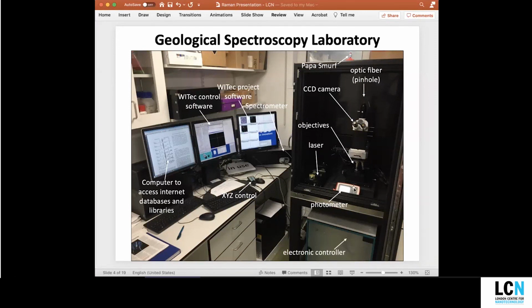And then there's also a photometer with which we can set the power of the laser, which can be set anywhere between about 0.1 milliwatts, even a few microwatts, but then you don't get a really good Raman signal, and all the way up to, well, it's rated at 65 milliwatts, but we typically don't go beyond 45 milliwatts. This is a class 3B laser, so there are some operational safety guidelines to consider for using it, but we also have a very versatile control software as well as the project software to process data and to do modeling, Lorentz peak fitting or Gaussian peak fitting, so that we can determine the areas under the curve. And we have, of course, Papa Smurf to help for good karma.